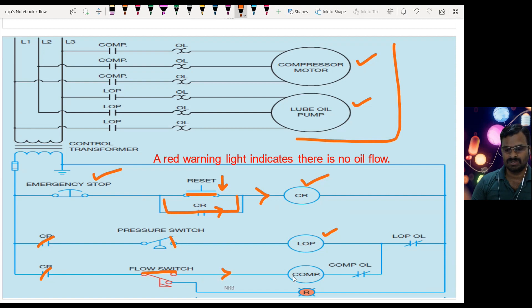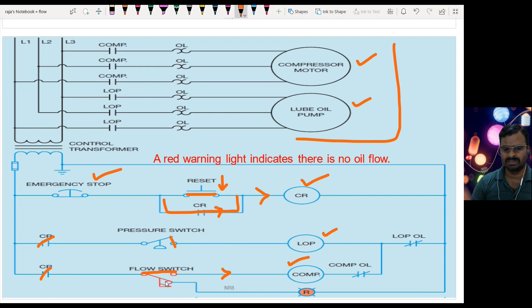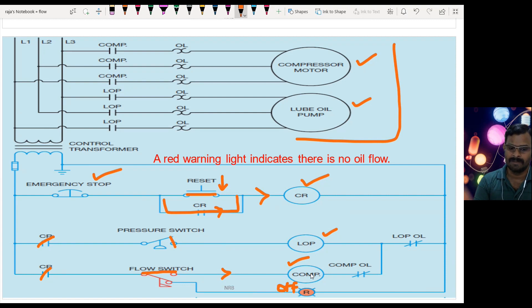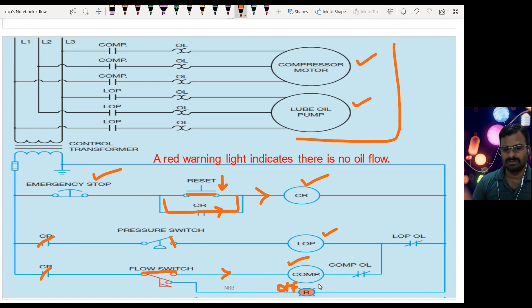When the flow switch detects liquid flow from the lube oil pump, the contact closes and current reaches the compressor motor, turning the compressor on. At the same time, the contact moves from NC to NO so the NC switch opens and the indicator goes off. This remains in on condition until the pressure switch releases. When the compressor keeps operating and pressure reaches a certain point, the pressure switch opens, the lube oil pump goes off, the flow switch opens, and the compressor also goes off.